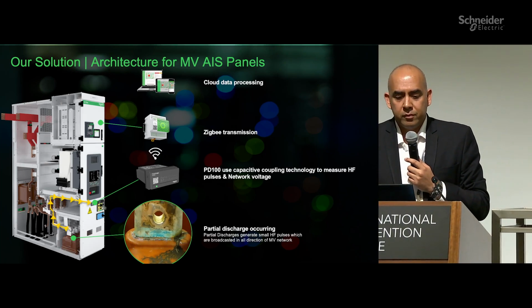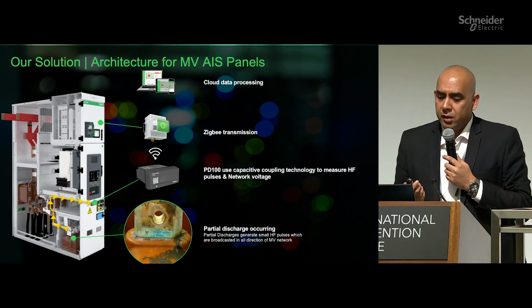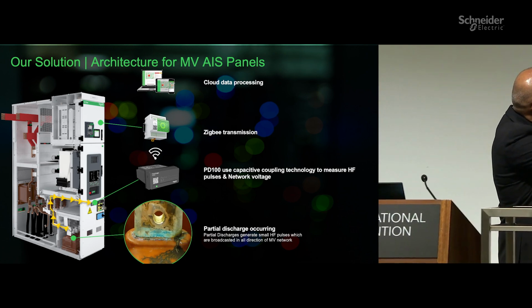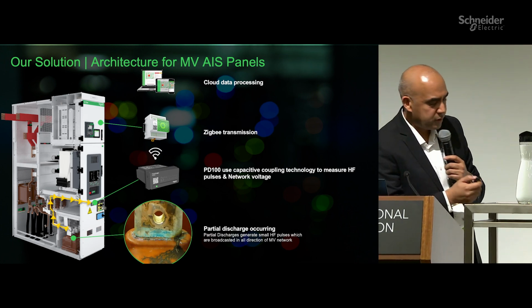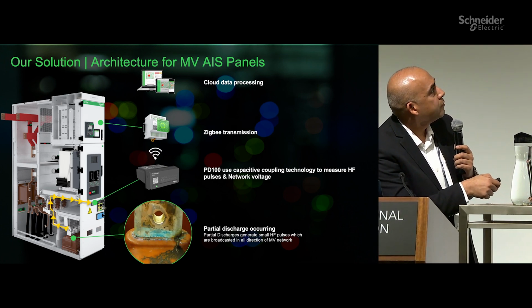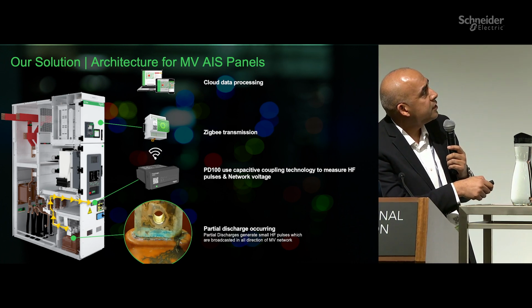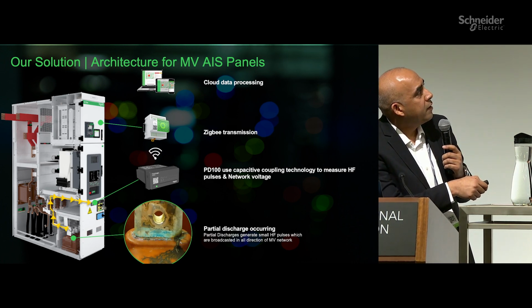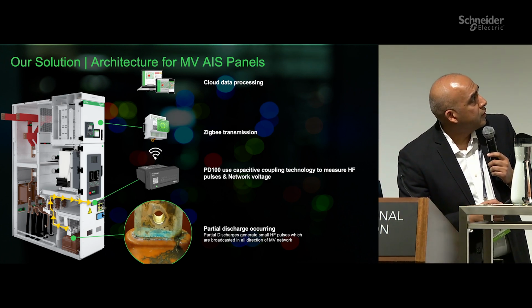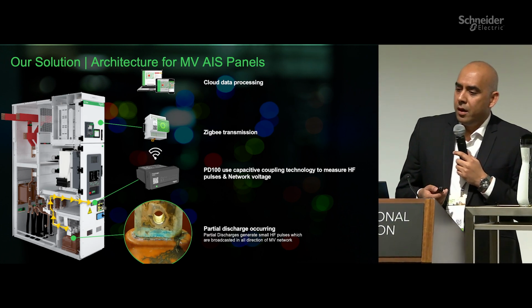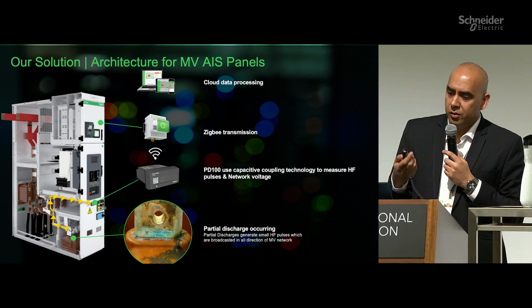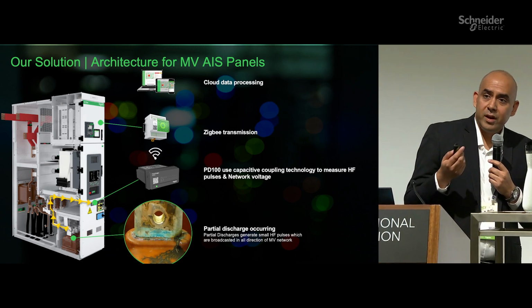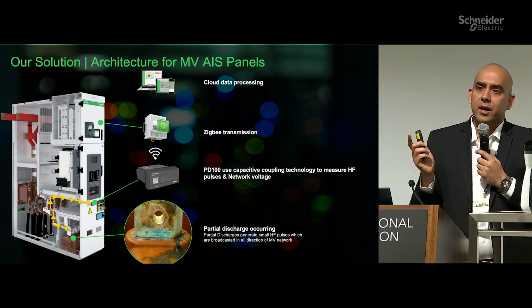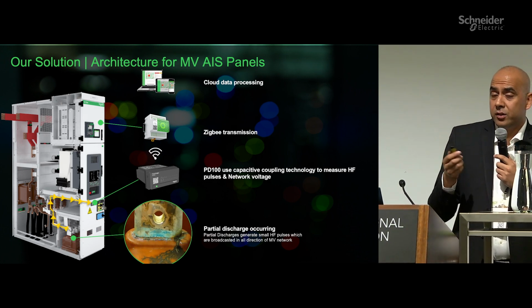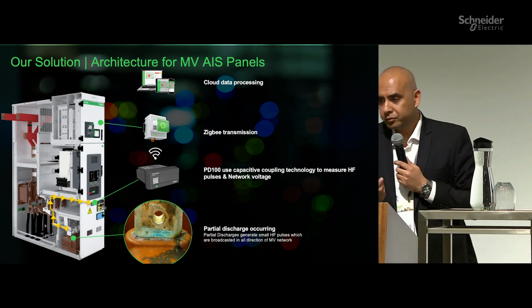Now, what's the architecture? How do we install the sensors? How does it look? So this is a typical MV switchgear panel. If you see, there is a partial discharge which gets developed, and we have a specific insulator. So we install a specific sensor here. This detects the discharge, and we have the coupler here, and we have the sensor which measures the partial discharges. We call it PD100. And we are communicating it to a system, a gateway, and it goes to our cloud processing program where we have all the analytics to analyze what is the kind of discharge and what could be the issue which is coming in. So this is the architecture, and again, available from day one.